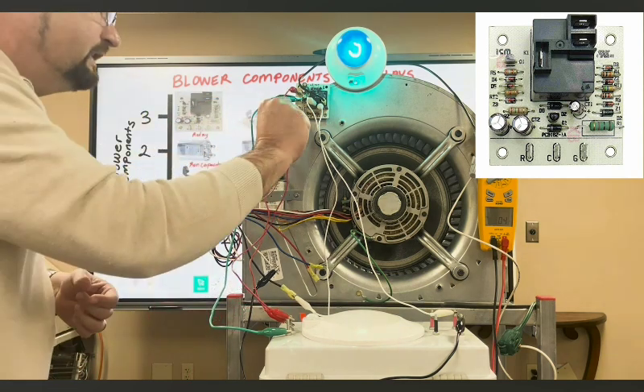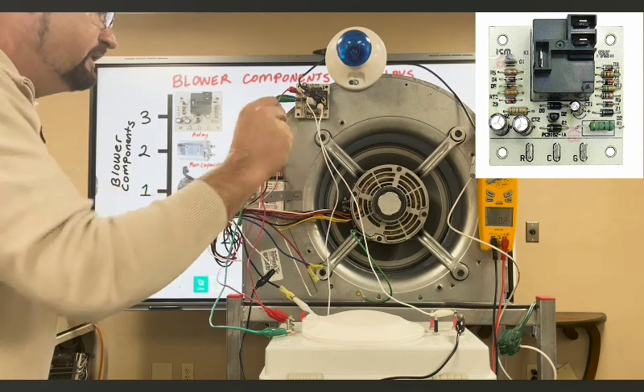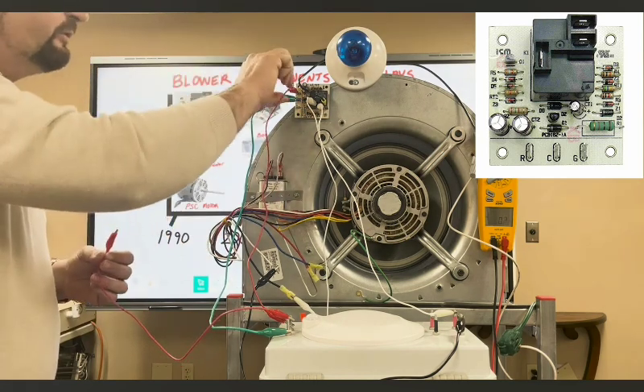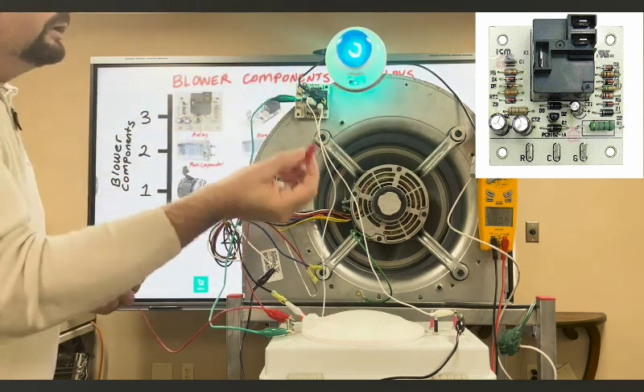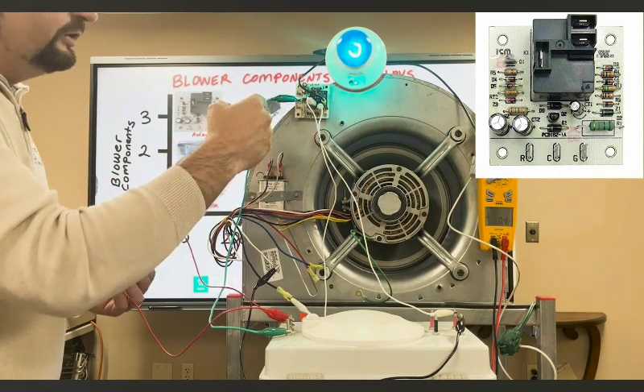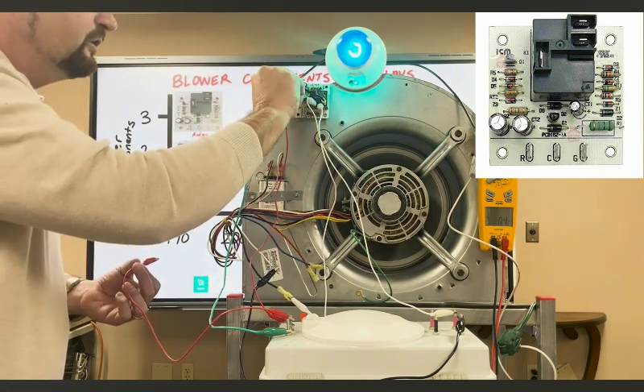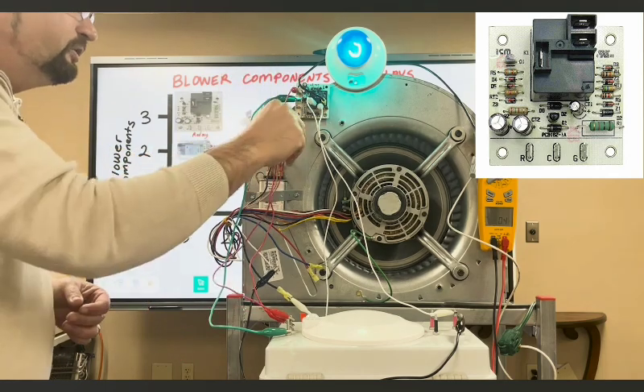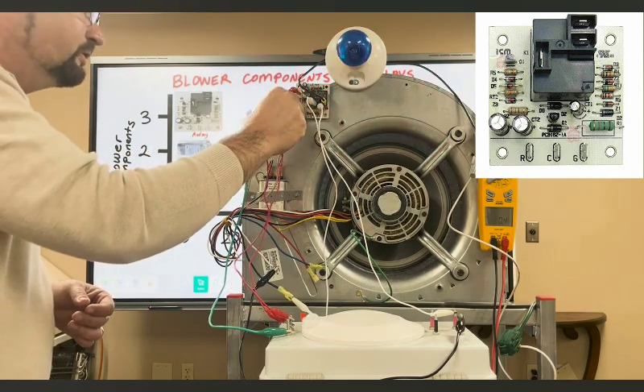I'll go ahead and show you again. I'm going to give it a G call. I'm going to take the G call away, and I'm going to remove 24 volts. And immediately, if the relay is good and not sticking, it should shut off. We're going to do that again. I'm just going to remove common just to show you it doesn't matter which order.